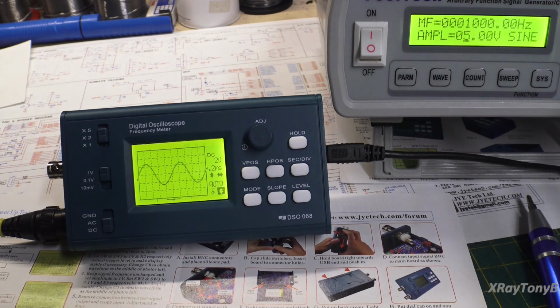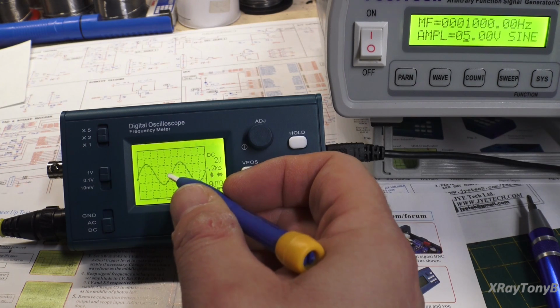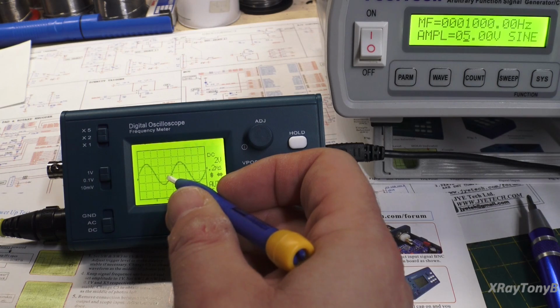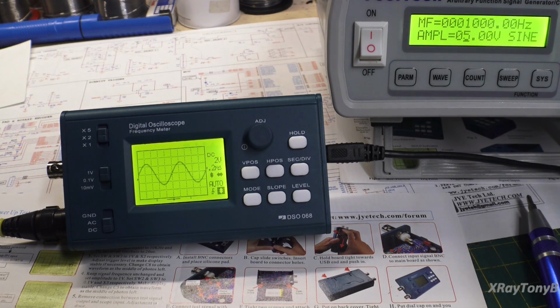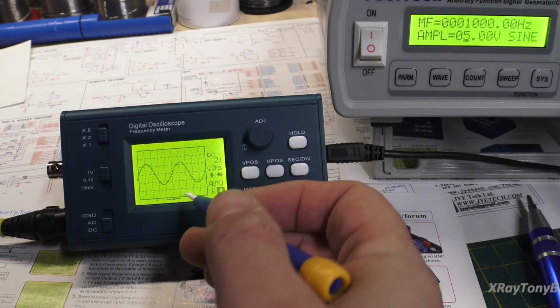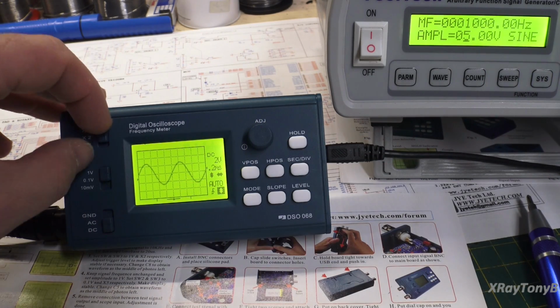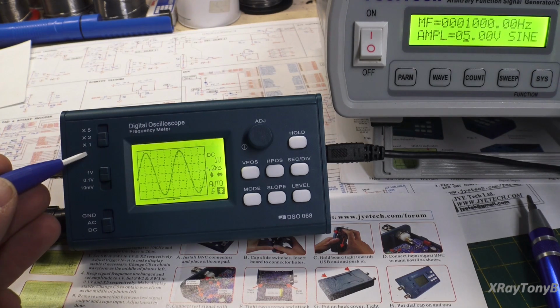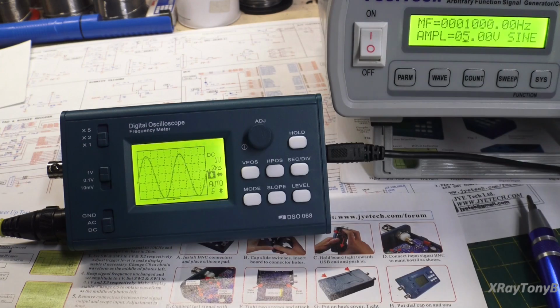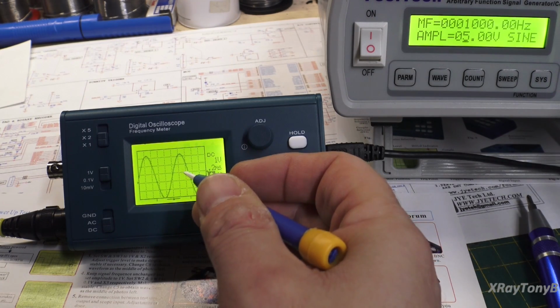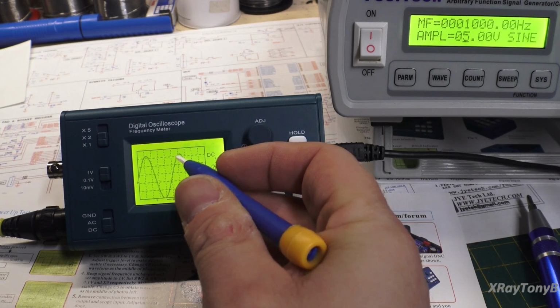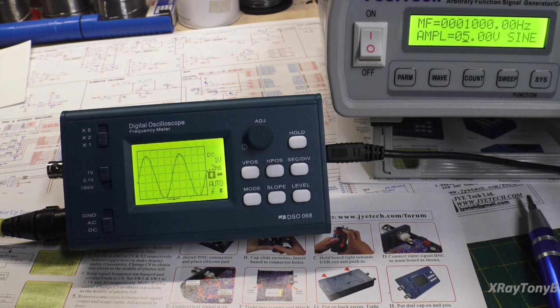So why did I say all this, and why are we looking at all this? Well, what that's telling us is this is accurately displaying a 1 kilohertz signal, and the scaling, our divisions, are actually accurate. Now, once again, we're looking at a 5 volt sine wave. So again, if we do our volts per division, I'm going to go 1 volt per division, and if I take my vertical position and I line it up directly on a bottom line, in a perfect world, what we should see is 1, 2, 3, 4, 5 volts. And you can see it's reading a little bit high. So once again, this scope isn't extremely accurate at measuring voltage, but maybe the signal generator is not outputting the signal accurately either.